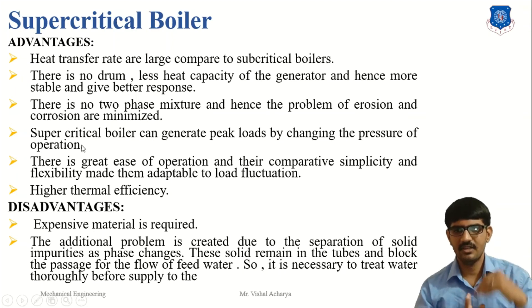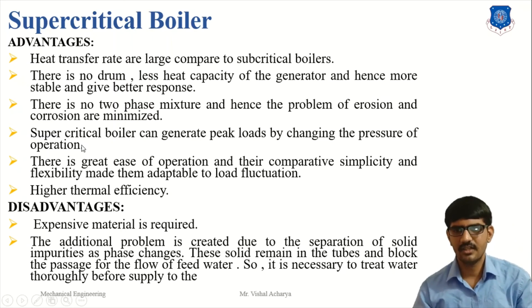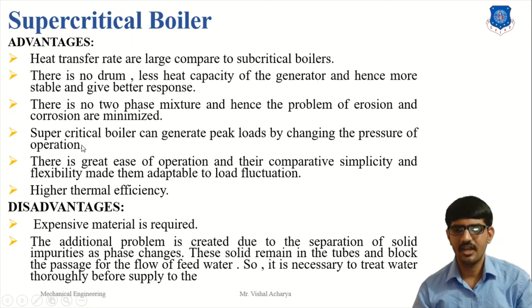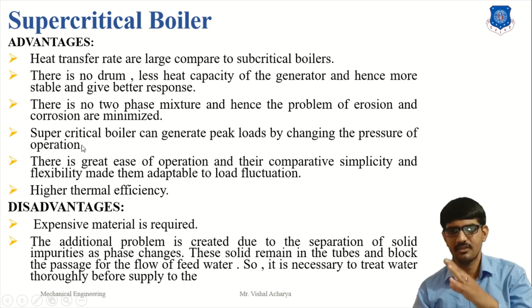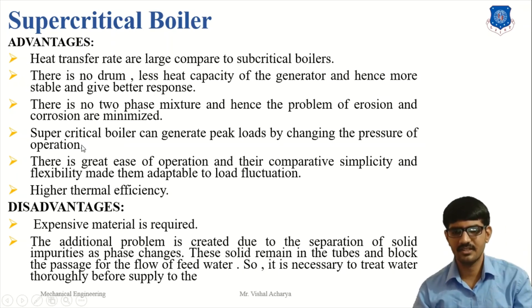In the supercritical boiler, the operating pressure is very high. Water pressure is the required main factor, and there is high thermal efficiency. However, expensive metal and materials are required. An additional problem is the separation of solid impurities as phase changes occur — the solids remain in the tubes and block the passage of water.